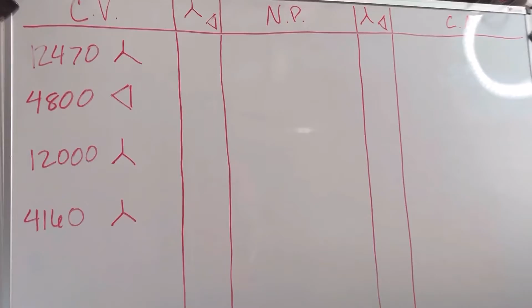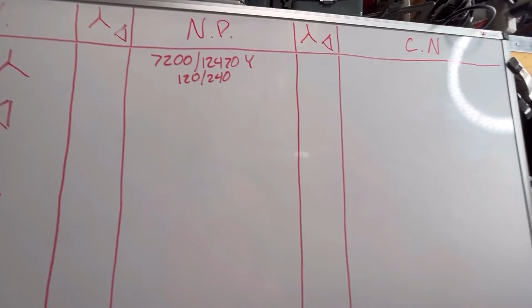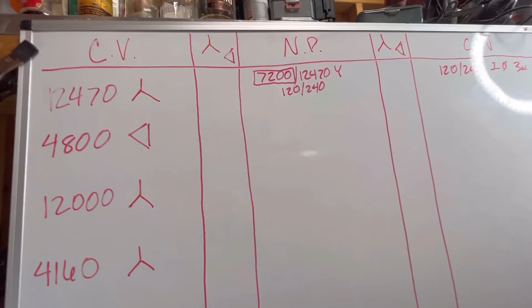So nameplate information, let's say this one is our favorite: 7200/12470 Y, 120/240 output, right? My customer needs 120/240, let's say single phase, 3-wire. Okie doke. So in looking at this one, we're going to say, okay, 12470. I know my transformer needs 7200 volts. So I'm going to use the primary input requirements of this transformer along with my circuit voltage to determine the hookup.